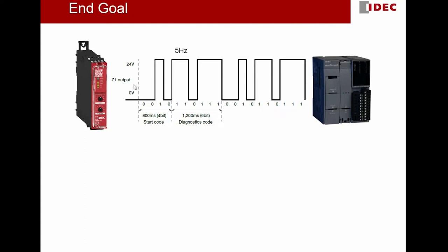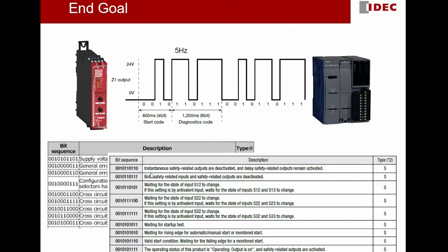We connect this Z-1 pulse output to our FC6A+ PLC and we will write a simple program to decode the diagnostic code so that by using this simple program we know the status of this safety relay. We will take reference from the HR6S safety relay manual to know the meaning of each diagnostic code and from there we know the status of the HR6S safety relay.